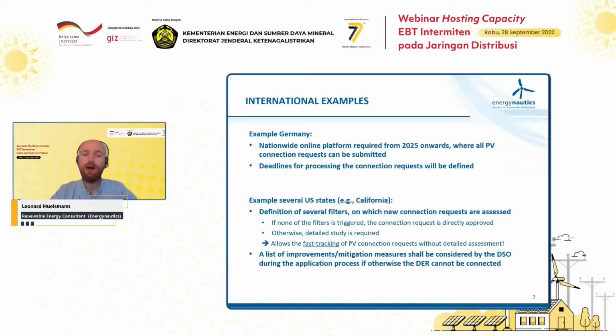In the US, particularly in California, several filters are defined on which new connection requests are assessed. If none of these filters is triggered, the connection request is directly approved. If one of the filters is triggered, then a detailed study is required. This is a good means to fast track PV connection requests without doing a detailed assessment every single time.